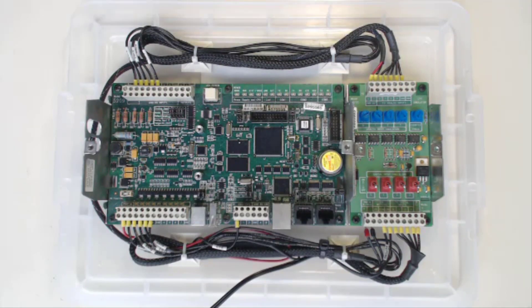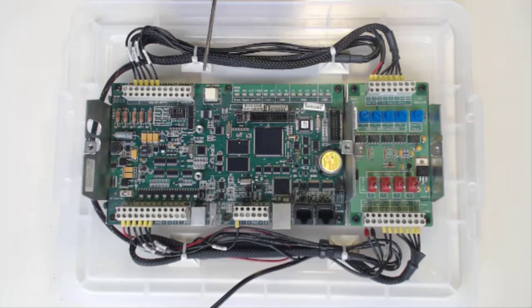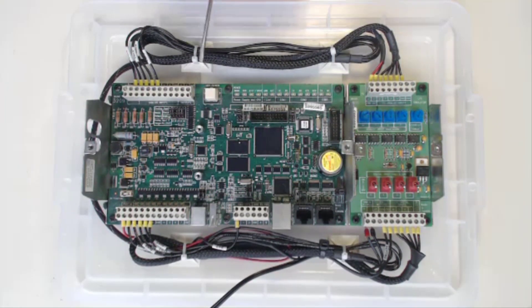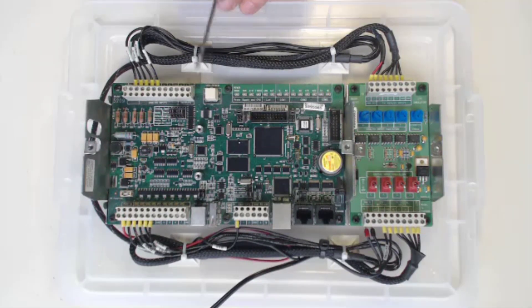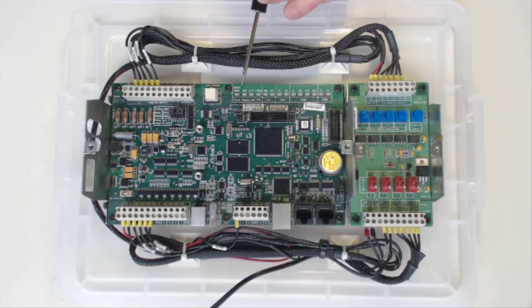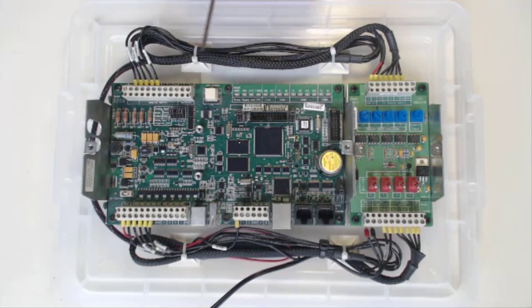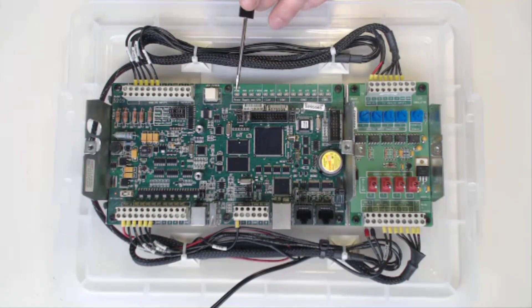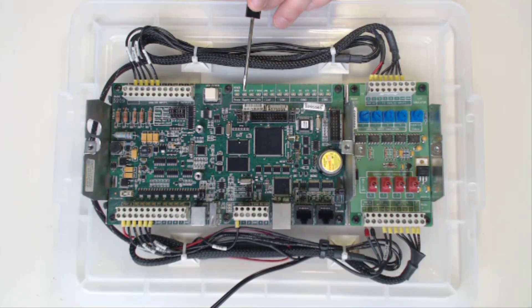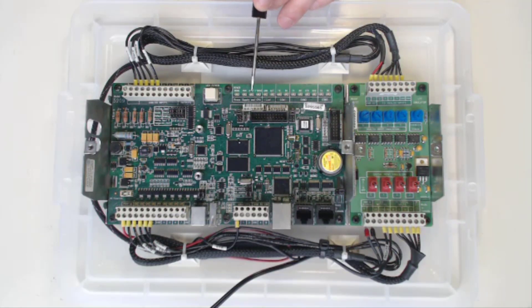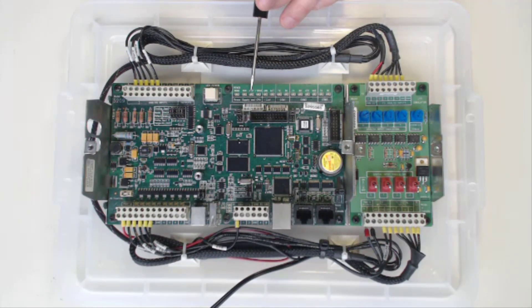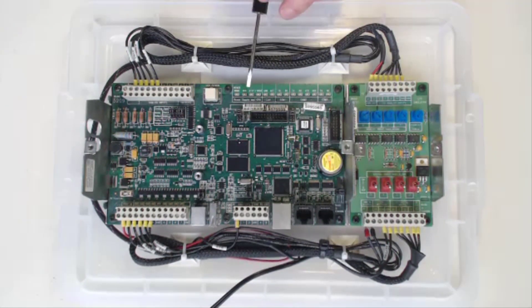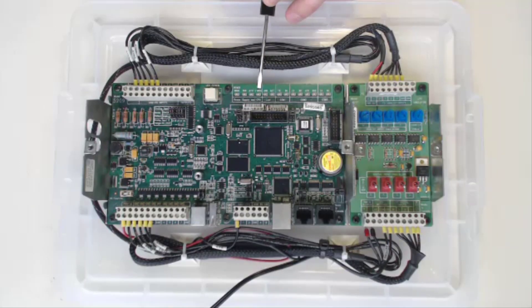Next is the LED power button. This is how you turn on and off the LEDs as well as reset the SNAP PAC. Next to that are all the LEDs. The first one is the power LED, so when you turn on power this light will turn on. Next is the run LED, so when the program's running in the system the run LED will be on. Next is the stat LED. If you have any bad statuses in the SNAP PAC, this will notify you. Next to that is the force LED. If you force any logic in your system, the force light will be on.